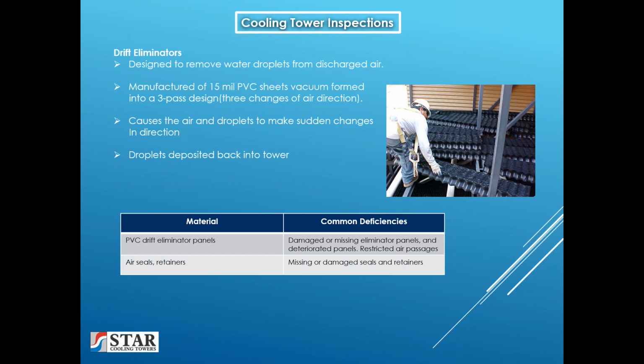The things you look for on an inspection are that there are no missing or damaged drift eliminator panels, that the air seals are properly installed, and that there are no accumulations in the air passages of the drift eliminators. Fouled drift eliminators can act like a plugged air filter on your car. It can actually choke the fan for air.